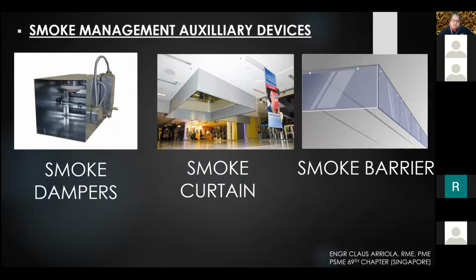And mind you guys, a smoke curtain is very difficult to maintain, because once it drops down, for example a full drop, which is 4.5 or 5 meters, I think some smoke curtain suppliers have difficulty rolling the curtain up. That's one of my experiences here when we were doing testing.